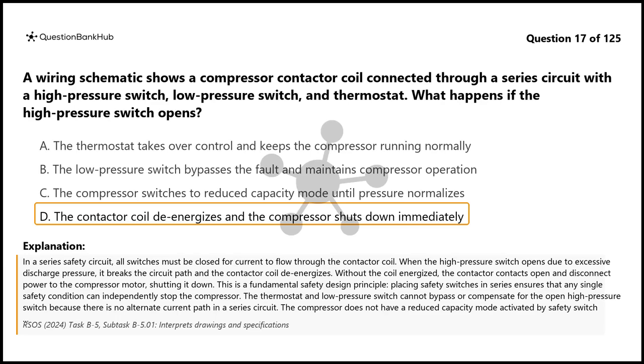This is a fundamental safety design principle. Placing safety switches in series ensures that any single safety condition can independently stop the compressor. The thermostat and low-pressure switch cannot bypass or compensate for the open high-pressure switch because there is no alternate current path in a series circuit. The compressor does not have a reduced capacity mode activated by safety switch operation. The system remains off until the high-pressure condition is resolved and the switch resets.